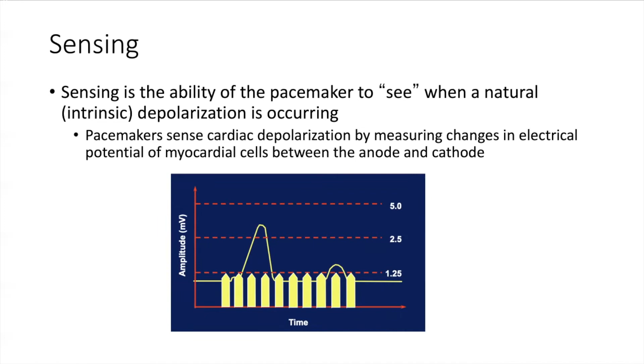Other terms you will see: undersensing. This means the pacemaker does not see the intrinsic beat and therefore does not respond appropriately. So you can see here that there's an intrinsic beat. The pacemaker doesn't sense it, and thus it delivers a scheduled pace inappropriately.